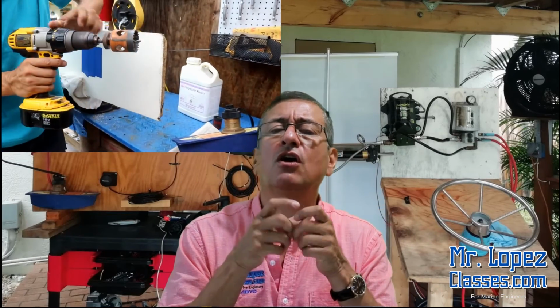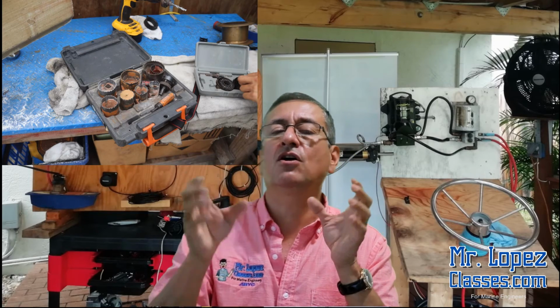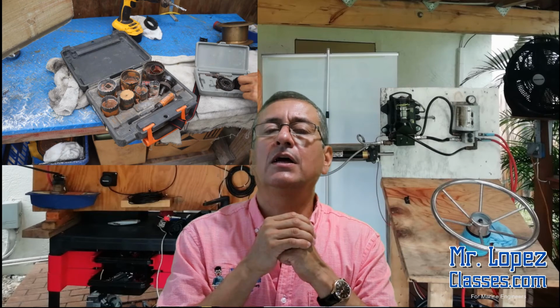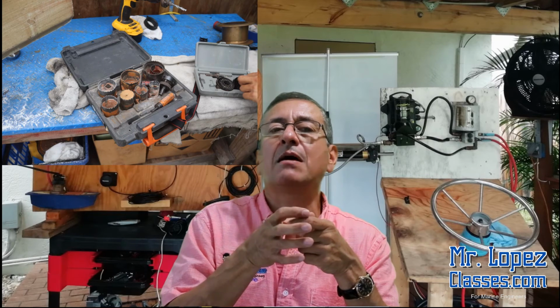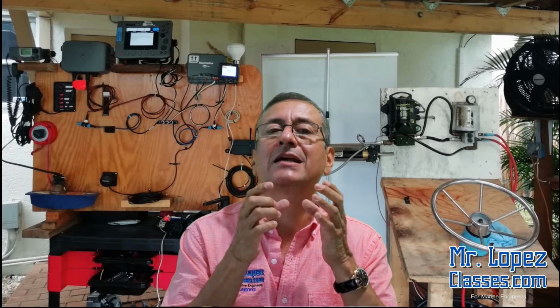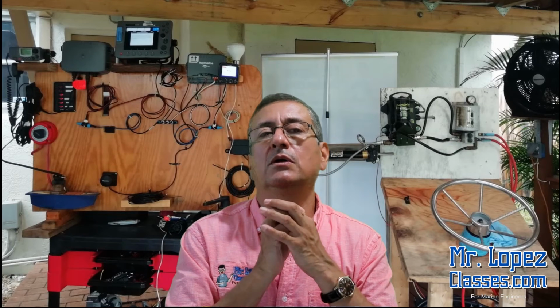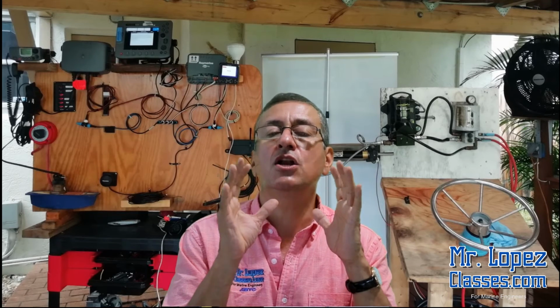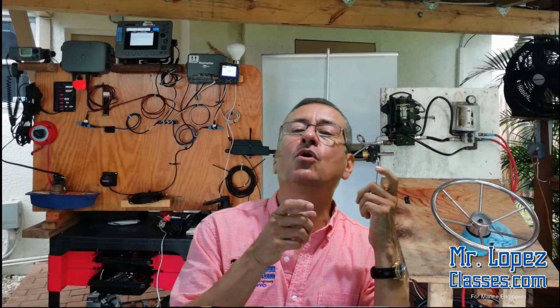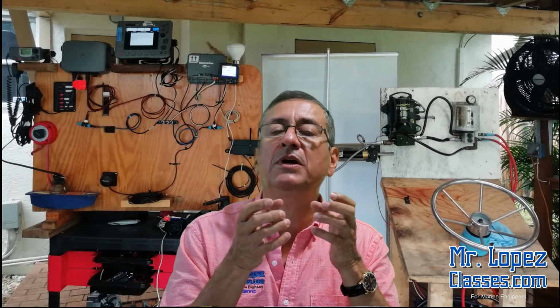You need to select exactly the hole saw appropriate for the body of your transducer. If you don't have the appropriate hole saw, I recommend trying to buy another set of hole saws, other brand, other manufacturer, because each manufacturer has different options in external and internal diameter. Be careful in the selection of the hole saw, and if you're not 100% sure, ask other technicians with more experience about that hole saw.